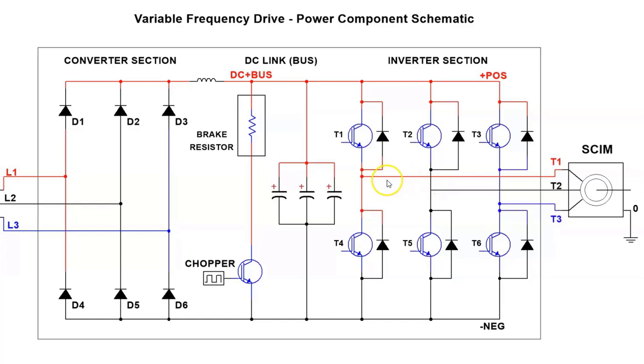Before I go over the power flow from the motor when it starts into generator action, I need to show you some circuitry that I added. I have added a chopper circuit and it consists of an IGBT and a controller that senses the bus voltage. It's part of the internal control circuitry of the drive. What the chopper does is it turns on and off and allows current flow through a braking resistor. The braking resistor can be internal, some drives have an internal braking resistor, or it may be mounted externally.